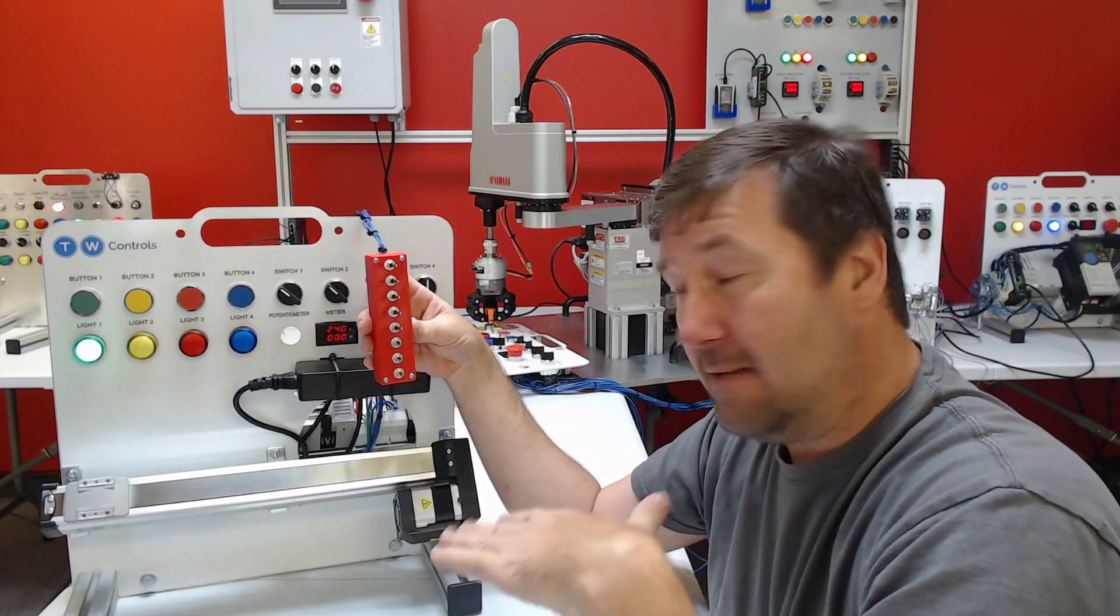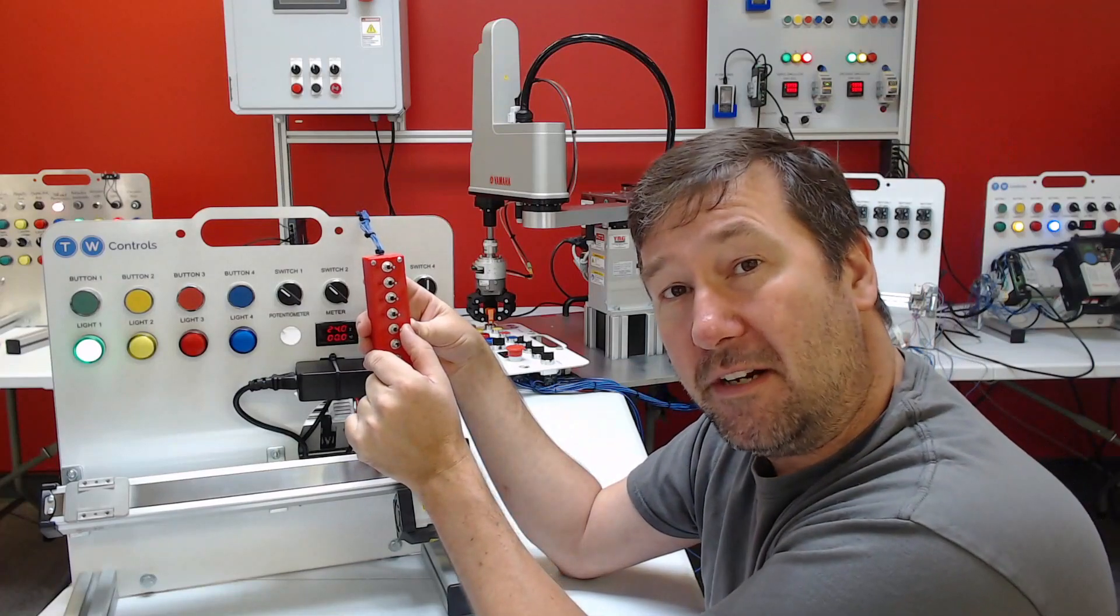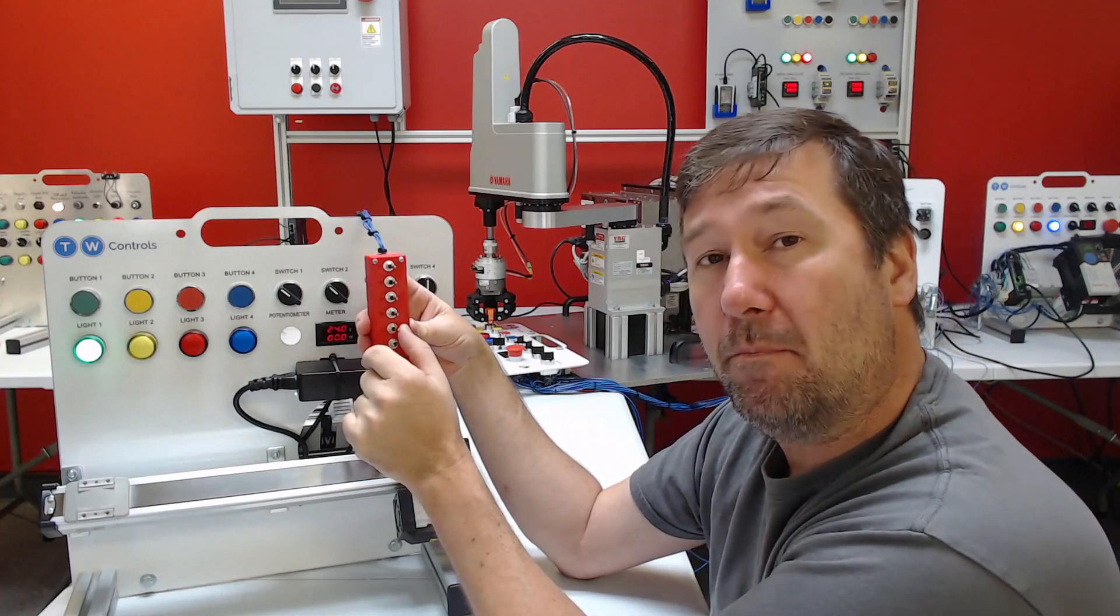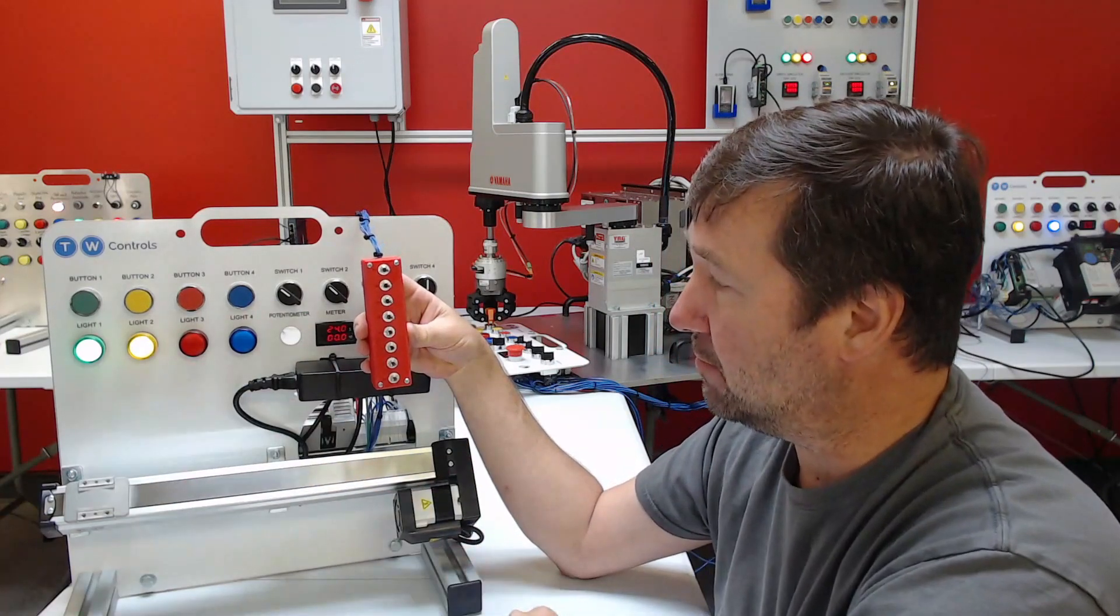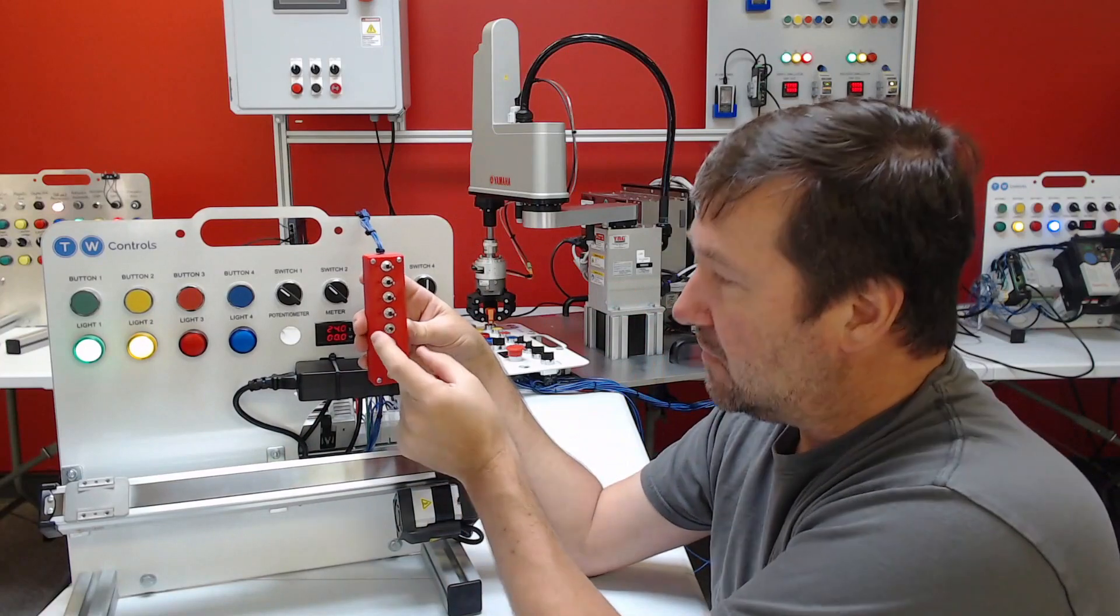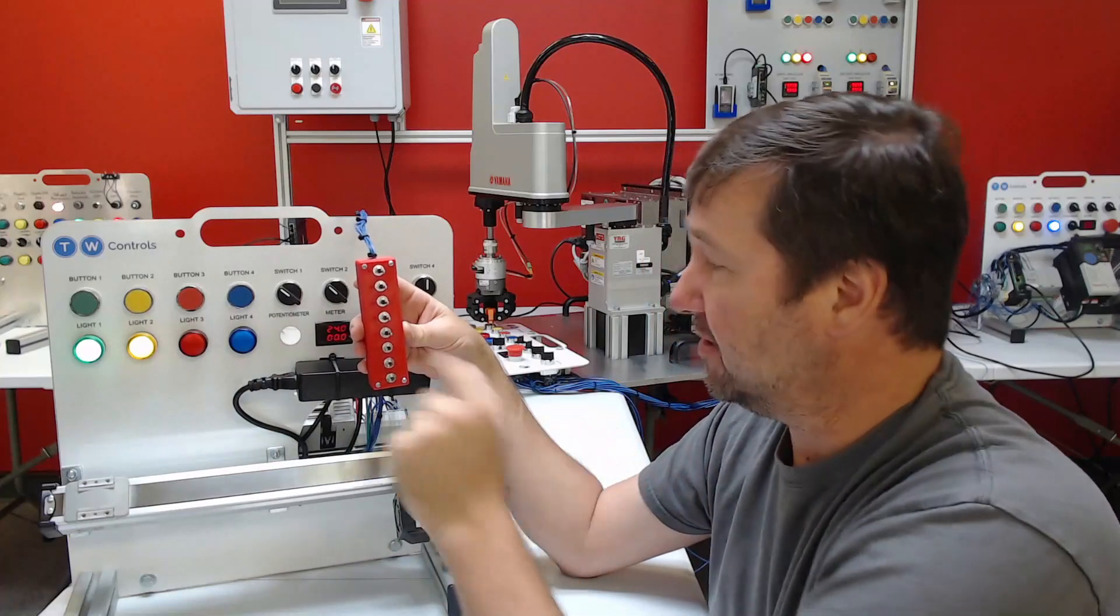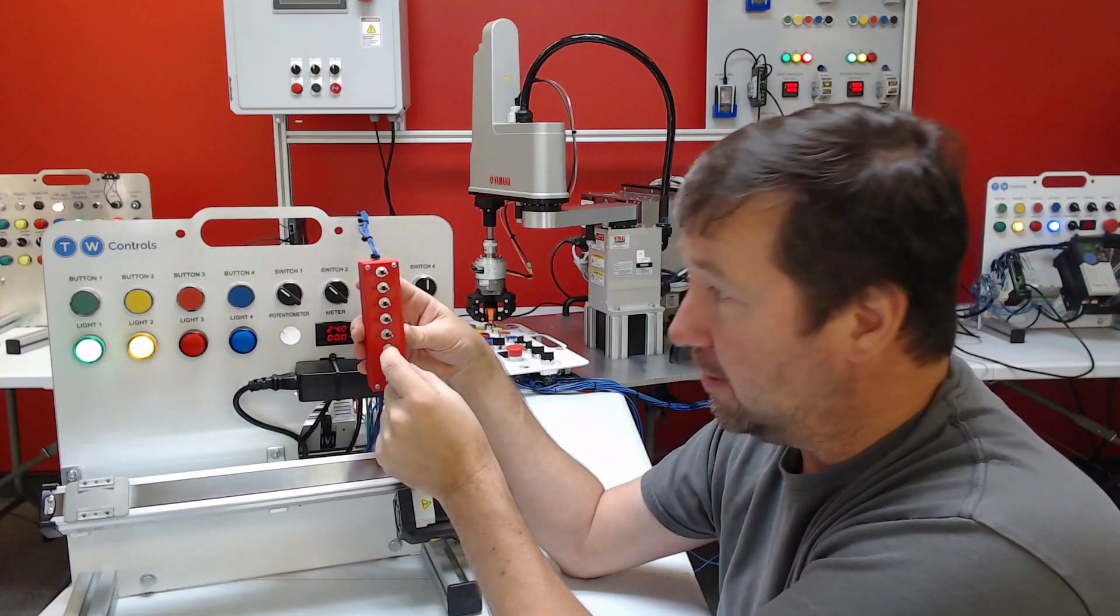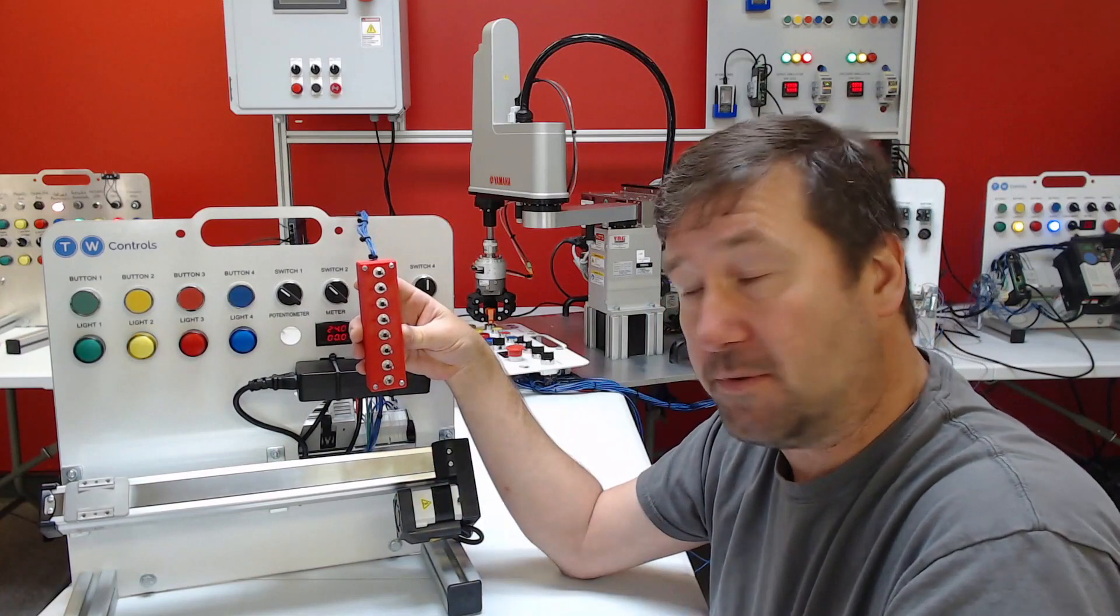Now let's say it can't keep up. So it's going to keep filling. And at this point we're hitting our lag float. And at that point both pumps should come on. So it does. And now we have pump 1 and pump 2 on. Now it starts drawing back down like it should. So we drop the lag float out. But notice they both stay on. They're going to stay on until the stop float. So then our lead float goes down. And then finally our stop float goes down. And that's when our pumps will shut off.